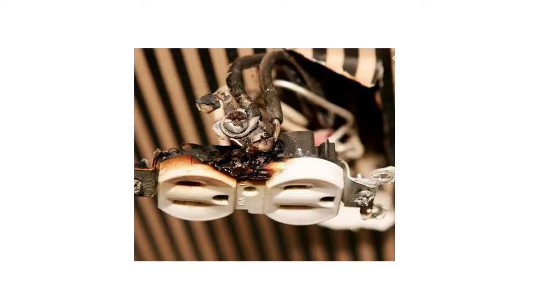In this case, we could have a high resistance arcing fault that either occurs from improper installation of electrical circuits or not identifying poorly maintained existing electrical equipment, and that circuit breaker will continue to conduct up to its rating until something happens. In the next couple of slides, you'll see the results of arcing faults, where the breaker failed to clear because the breaker thinks that it's just conducting power up to its rated capacity. And I think that most people may have experienced this in their homes. They've seen these images, burnt electrical receptacles.